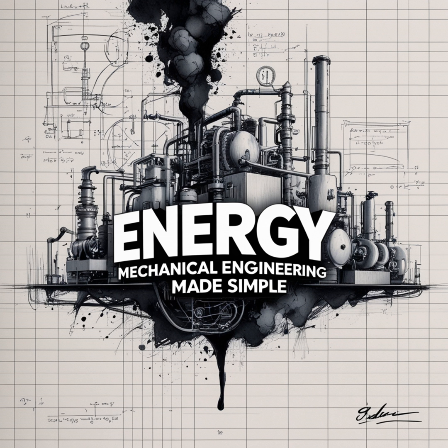Absolutely. That's the crucial trade-off. Turbulent flow gives you much better heat transfer, but you pay for it with significantly higher friction losses. This means you need a more powerful fan or pump, using more energy, making more noise. So engineers aren't just blindly chasing the highest possible turbulence. No, not at all. Good design finds the sweet spot. Often just getting into the turbulent regime gives a big boost, but pushing Re higher and higher might give diminishing returns on heat transfer, while the pumping power cost skyrockets. It's always an optimization game.